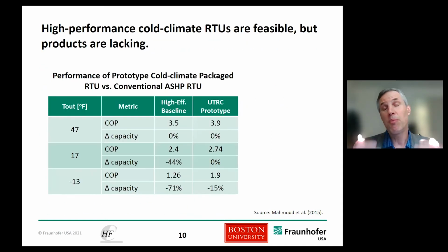So there have been DOE funded projects to look at this for high performance units. This is work done by United Technologies Research Center, owned by Carrier back then, and this was done 5-6 years ago. You can see at 17 degrees out, you're seeing a 44% capacity drop off in the high efficiency baseline. No drop off in capacity in this unit. Minus 13 degrees Fahrenheit, pretty darn cold, colder than it really ever gets around here in Boston. Normal unit, 71% capacity drop off, a COP about 1.25, but the prototype unit was almost a 2 COP and only a 15% capacity drop. So this is feasible, but there's a lack of market demand for these products.